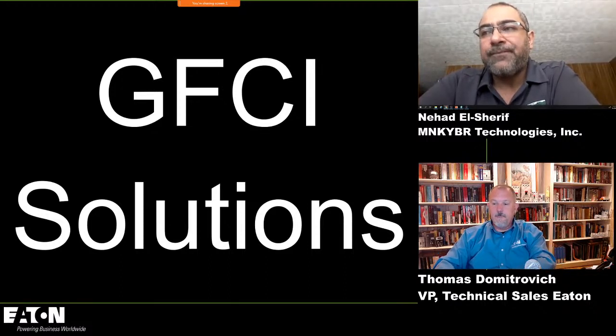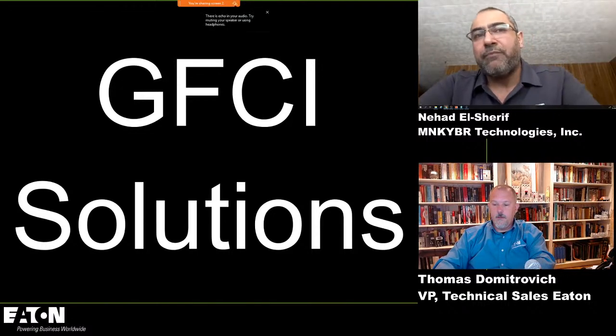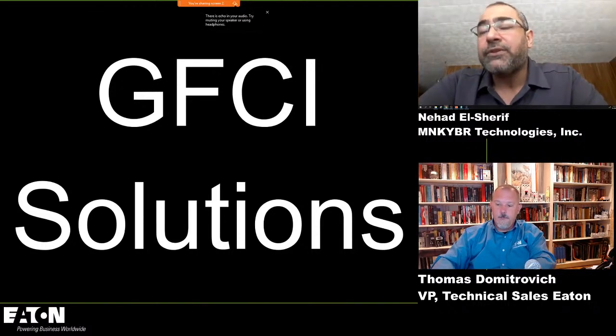The device is constantly testing itself, and it would interrupt power or give you some indication, whether visual or audio, that there is a problem in the device itself if there is a failure in the electronics. So this was all driven by the fact that most people don't test GFCIs in the field.